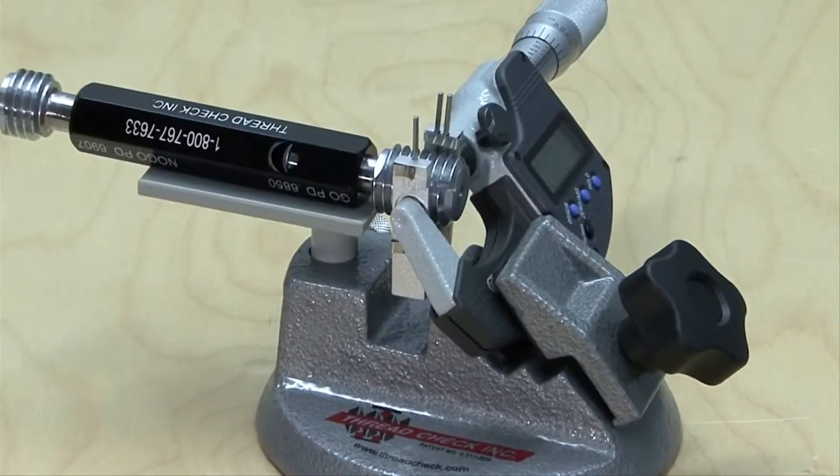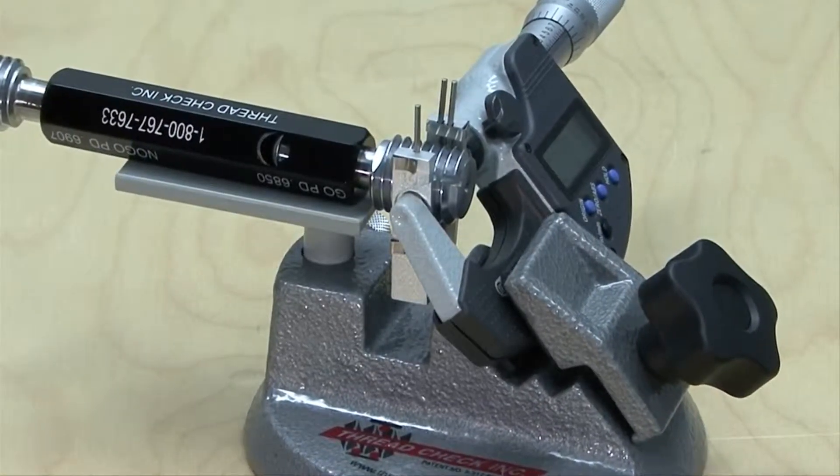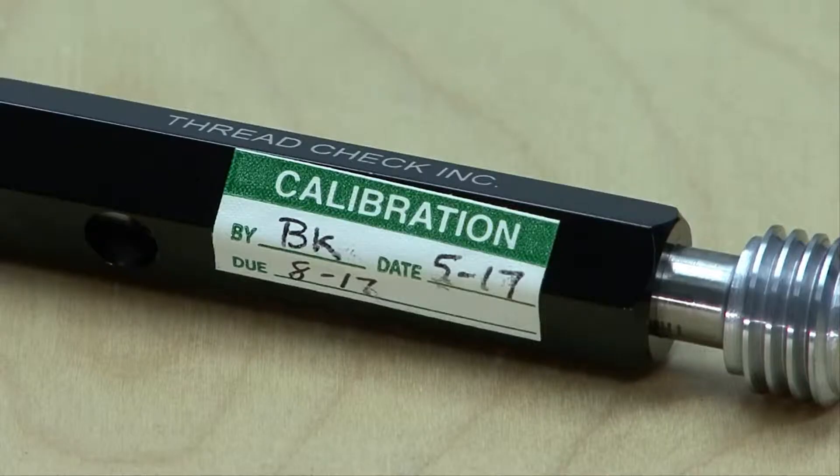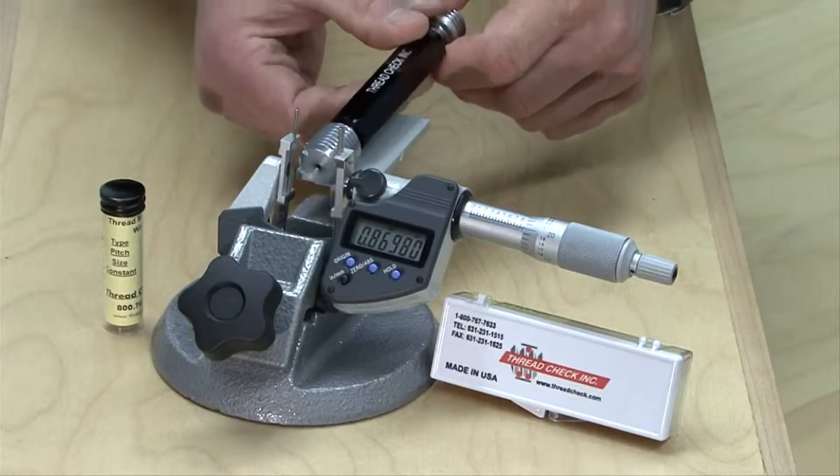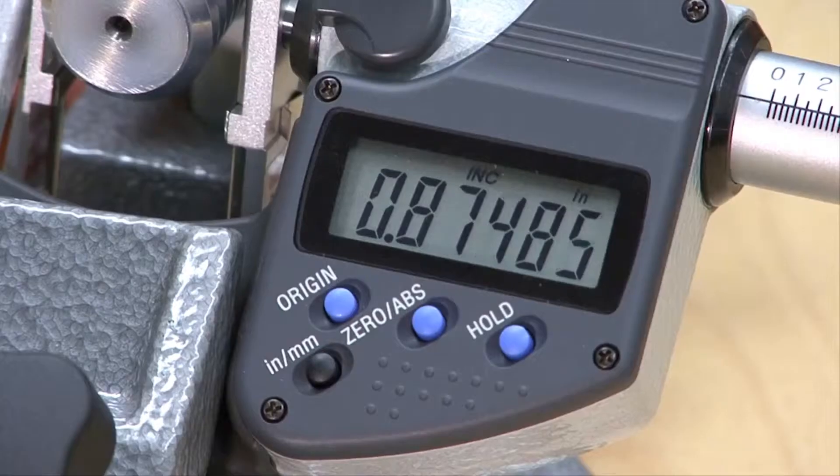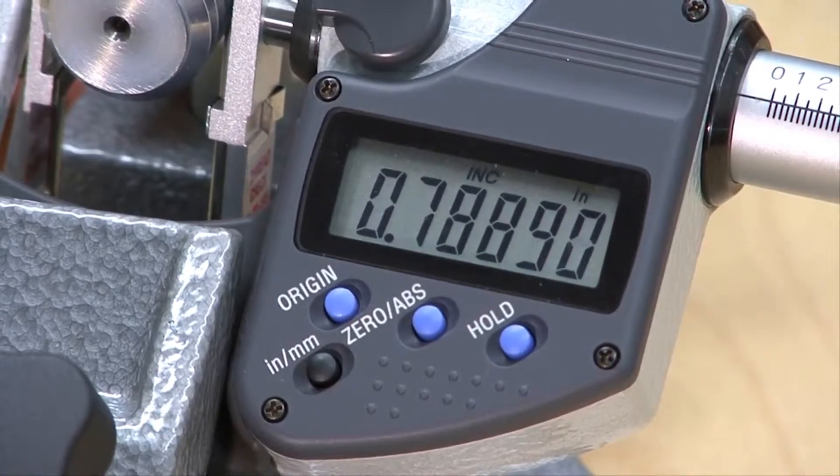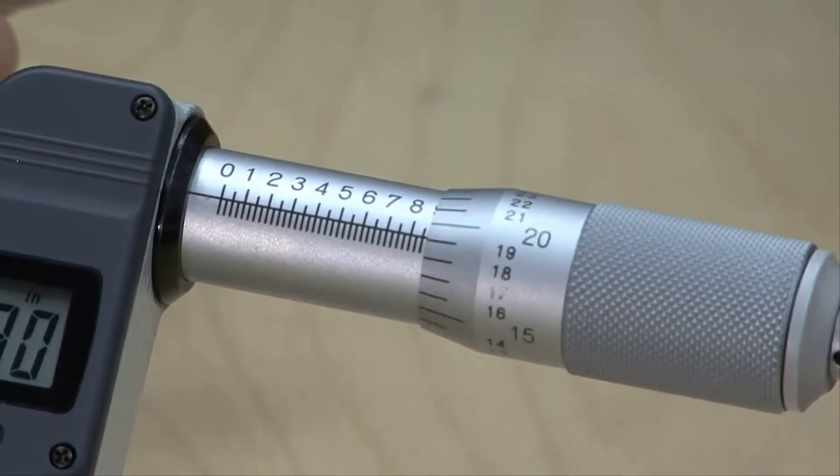The inspector should confirm the gauges are calibrated. It is always advisable to recheck the thread plug gauges prior to use regardless of the calibration sticker's current status. Many companies arbitrarily select annual frequencies of calibration rather than basing frequency on usage. This can create quality issues as thread plug gauges can be worn out of tolerance or damaged during the course of a production run.